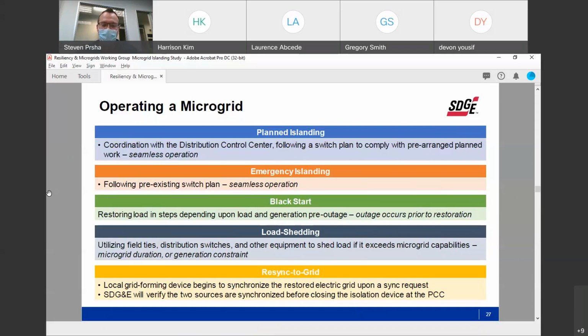Lastly, once we're finished with an island and the grid is back, we need to resynchronize the microgrid with the grid. This is actually a 2-step process. The grid forming device - Harrison mentioned the generators are currently our grid forming device in Borrego - and we're looking through some new efforts to convert that to a battery, most likely.